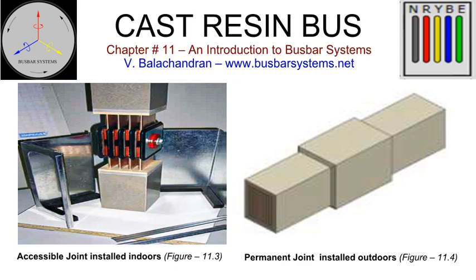When a cast resin bus is installed outdoors, the site joint can be carried out by bolting the factory-made fish plates and encapsulating it with a resin compound by a process similar to cable jointing. It also provides some flexibility in compensating for minor variations in length along the axis of the cast resin bus during installation. Standard elbows, bends, tee-offs, transpositions, tap-offs, and termination ends are available for various current ratings. A few manufacturers find it convenient to have all bends cast at the site for ease of installation.